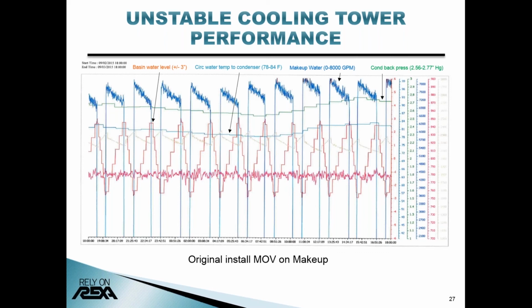Sure, Rich. Starting with the basin water level. In a very crude control scheme, we were allowing our basin water to operate between -3 inches and +3 inches in just an open and closed control scheme. The makeup flow, shown in the blue line, was going from 0 to 8,000 gallons when we opened the valve, and then as the tower filled to 3 inches, we would close the valve and allow the tower to evaporate off down to a -3, and then we would simply open the valve again.